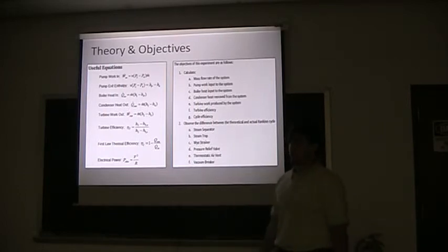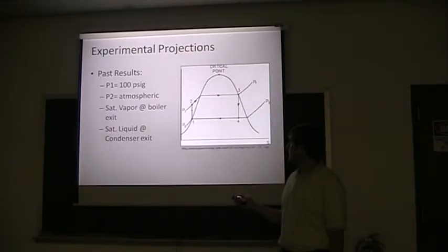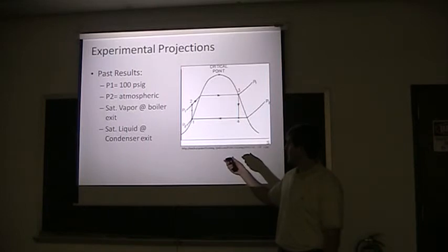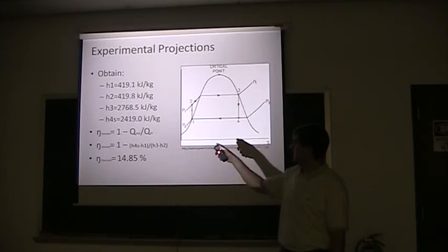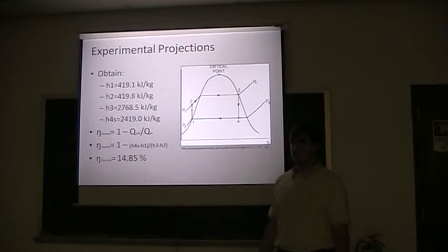And then some of these objectives we want to do, we want to find the efficiency, big ones, we want to find the efficiency of the turbine, and we want to find the efficiency of the cycle. And we just want to know what some of the stuff to do, like to see some of the steam trap. Okay, for our objectives, the past results said they had a P1 of about 100 psi gauge, and P2 is atmosphere. And then points saturated vapor at the boiler exit, and then saturated liquid at the condenser exit. So, using those numbers, I got our H2 here, and then that gave us a thermal efficiency of 14.85, which is kind of low.